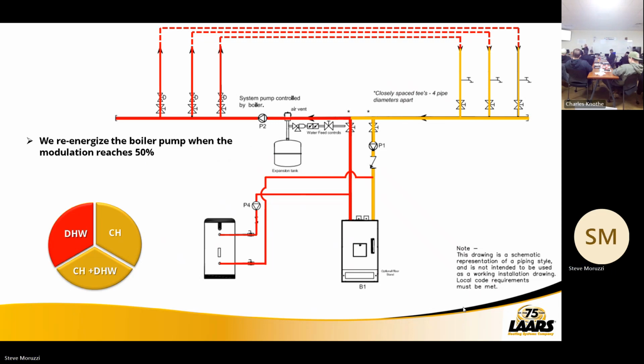So you guys would very rarely see this happen. It happens, but it's not something that the end user is going to see. Does that make sense? Because you still have some flow out in that system when we keep that system pump energized. You're not going to dissipate that heat in a matter of 30 seconds. Okay? You're still running that heat loop. All right. And if you don't like that, you can go back to regular or traditional priority is your other option.